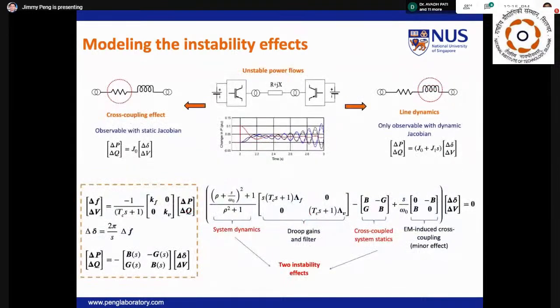Suppose we now replace the infinite bus with another grid-forming inverter as shown in the center single line diagram. The interaction between these two inverters under high Droop gains will result in unstable power flows as a consequence of these two destabilizing effects. If the line has a high R by X ratio, then the instability is a direct result of the PQ cross-coupling effect. If the line has a low R by X ratio, then the instability is an outcome of the lagging dynamics of the line. These two effects can be represented by these terms in the fifth-order model shown here.